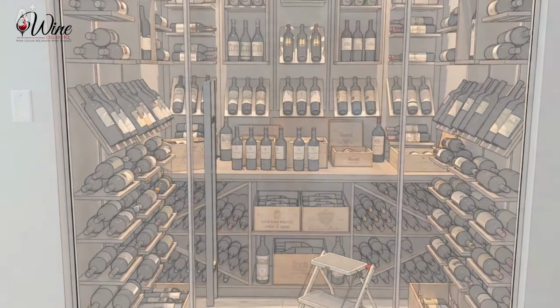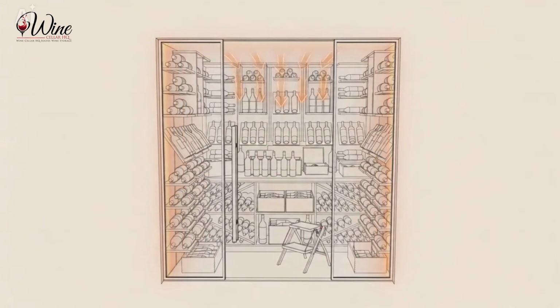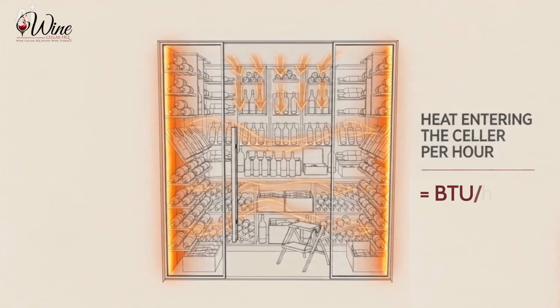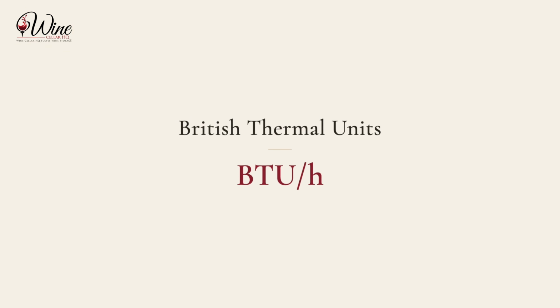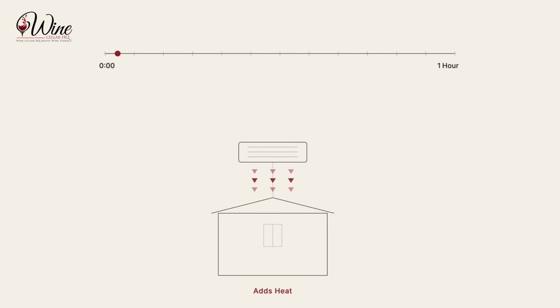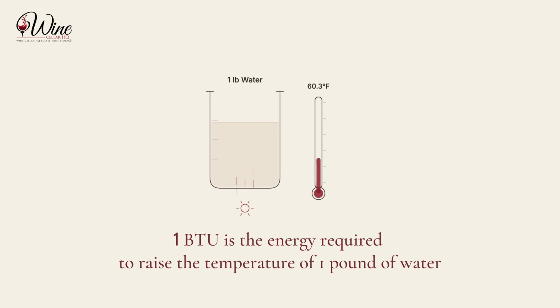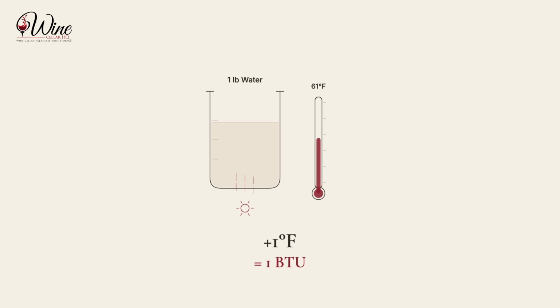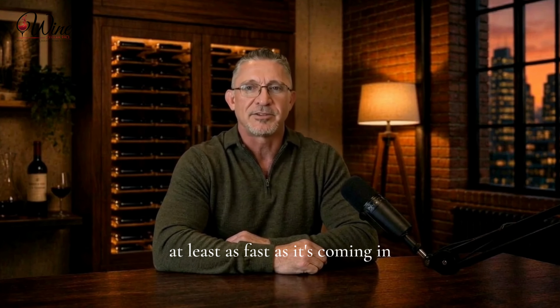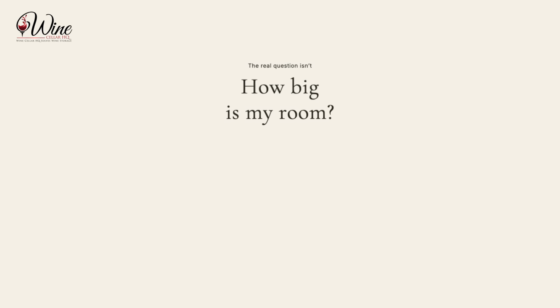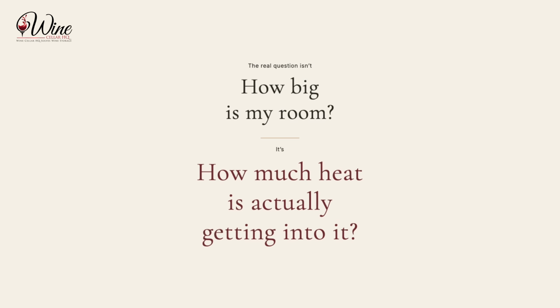Here's the concept that actually determines which unit you need: heat load. Heat is always trying to work its way into your cellar, through the walls, the ceiling, any glass, even the door every time it opens. Heat load is simply how much of that heat is entering every hour, measured in BTU per hour. BTU per hour stands for British Thermal Units per hour. It measures the amount of heat energy an appliance can add to or remove from a space in 1 hour. 1 BTU is the energy required to raise the temperature of 1 pound of water by 1 degree Fahrenheit. Your cooling unit's entire job is to remove heat at least as fast as it's coming in, so the real question isn't how big is my room, it's how much heat is actually getting into it. Those are two very different numbers, and mixing them up is where most sizing mistakes start.